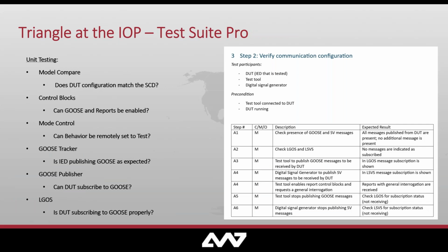So moving along, the next tool we brought to the IOP, Test Suite Pro. During unit testing, Test Suite Pro was connected to a single IED under test, or device under test, at a time. And we would follow a detailed unit testing script, some of which Christoph described earlier, and you can also see in the diagram here on the right.